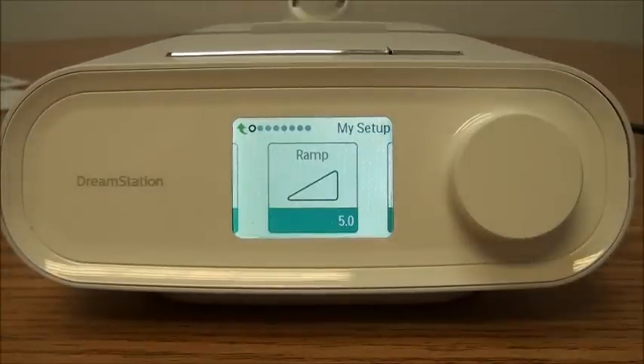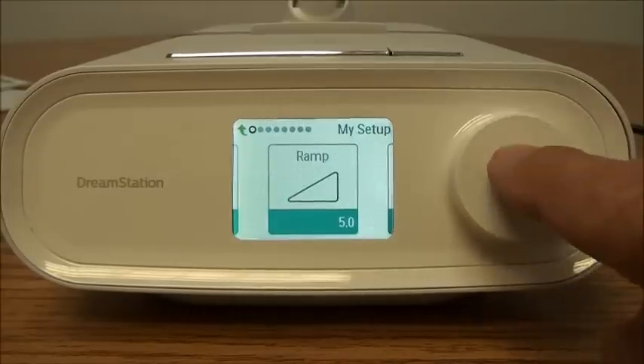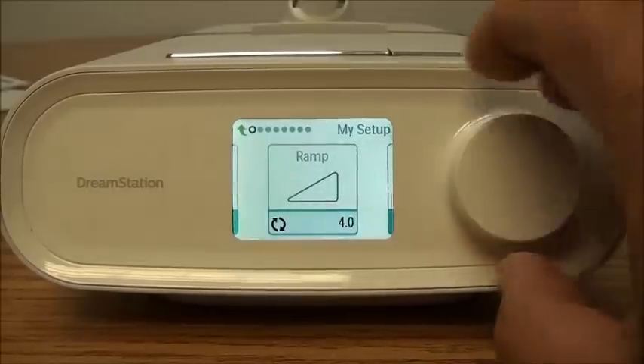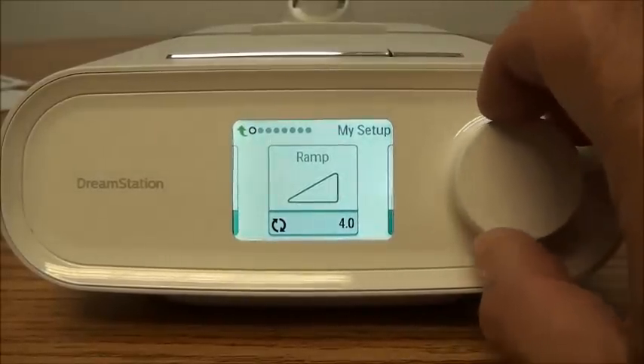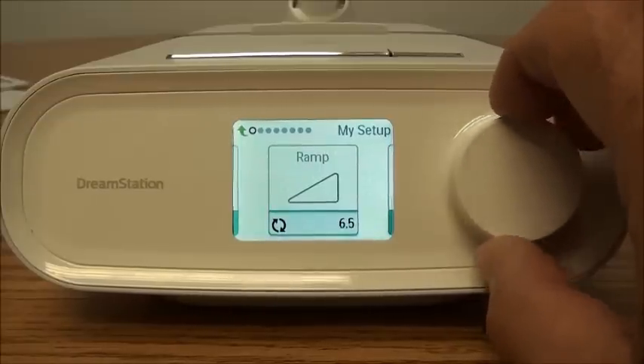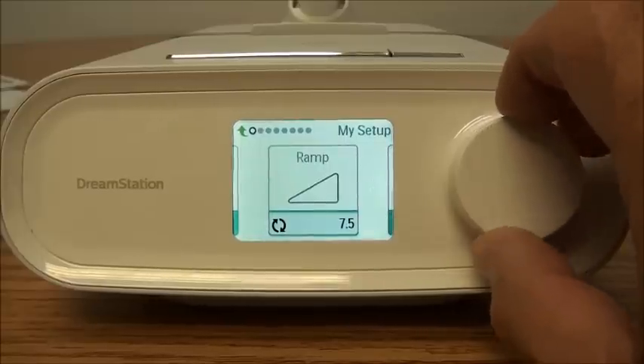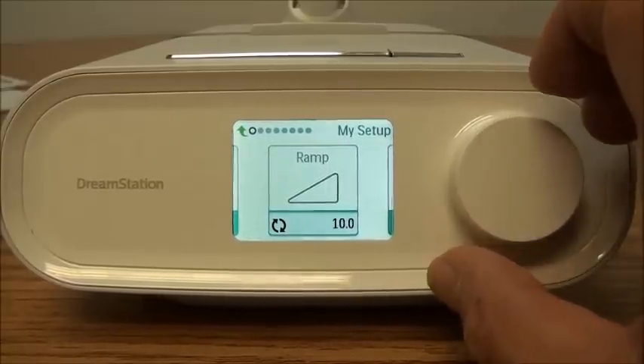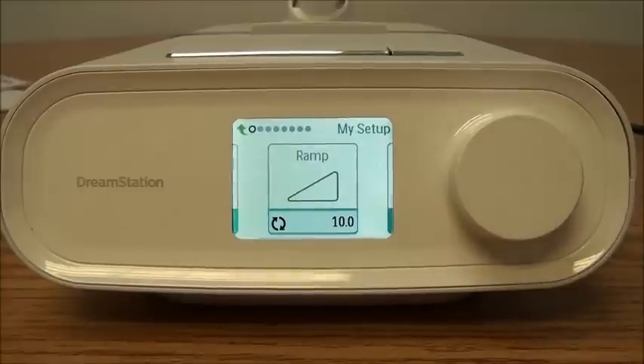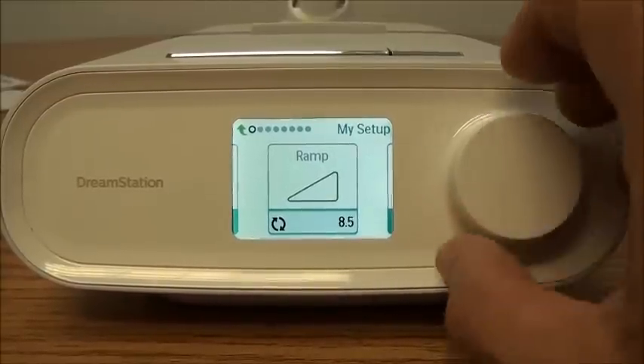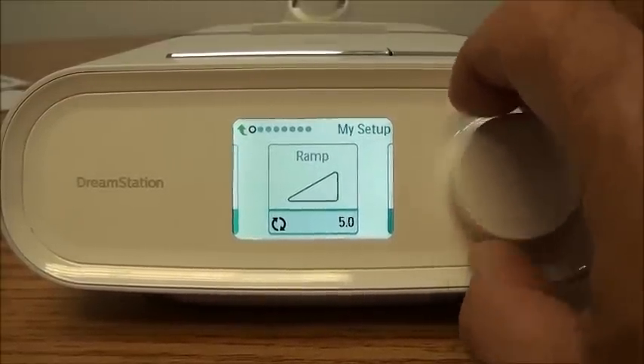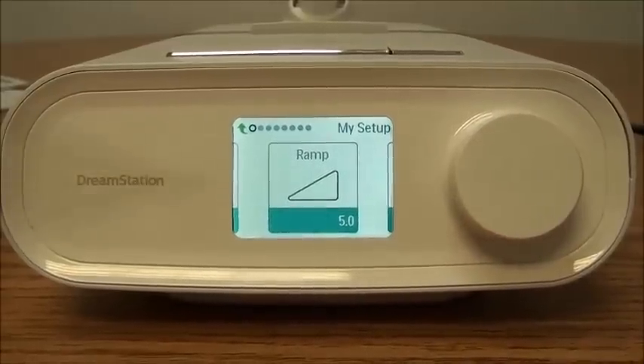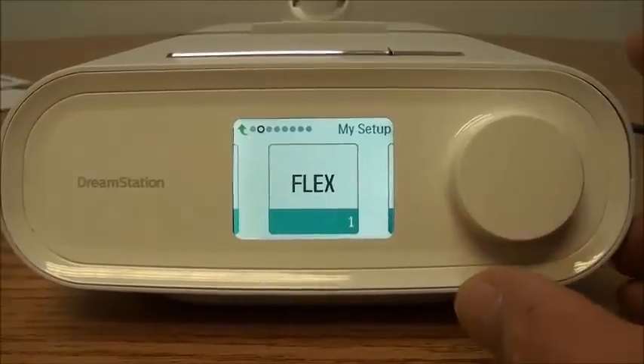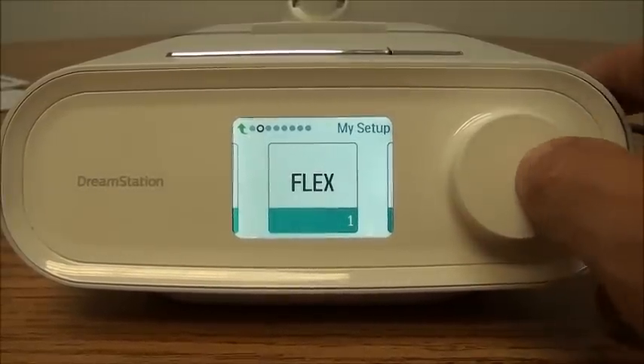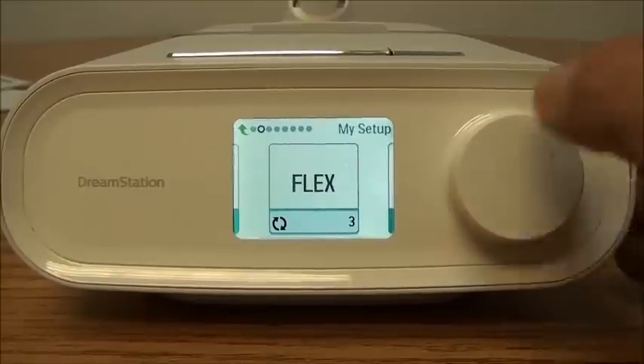As you remember, we discussed the ramp function earlier, but you're able to adjust the start point by depressing the button, and in this case you can start your ramp at 4 centimeters of water pressure, and since we have this machine set at 10 centimeters of water pressure, you can adjust this all the way up to 10 centimeters of water pressure. So that's where the ramp would then start. In this case scenario, we're going to start at 5. Okay, so that is set. You can adjust the flex mode on your machine by depressing the button and adjusting it from 1 to 3.